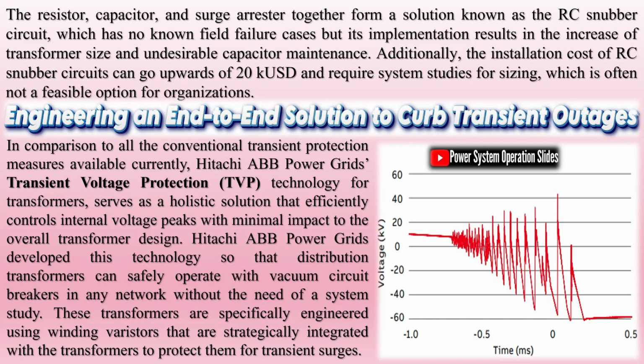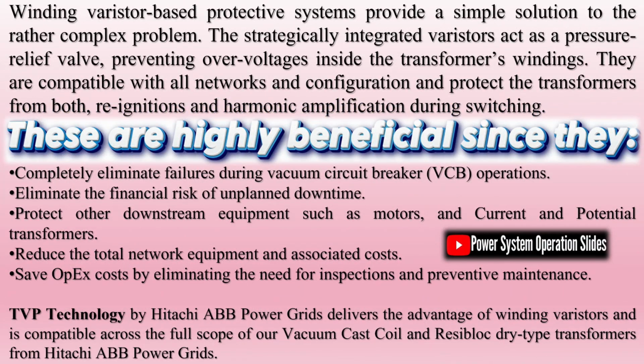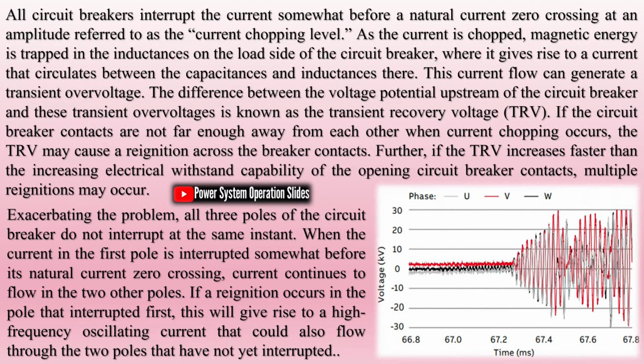This issue is usually addressed by combining a surge capacitor with an arrester. While this helps in slowing down the rate at which the overvoltage rises and capping the peak voltage, it does nothing to offset direct current (DC). Besides this, there is another way to restrict current chopping virtually. By integrating a resistor with the capacitor and the arrester, grid administrators can reduce the DC offset of the transient overvoltage waveform and reduce the potential of virtual current chopping.